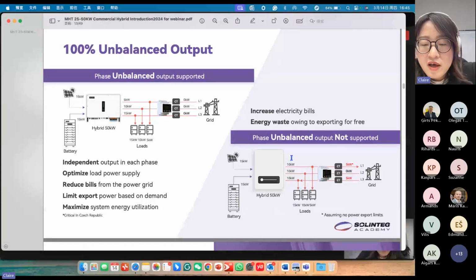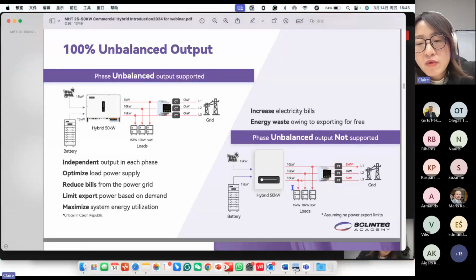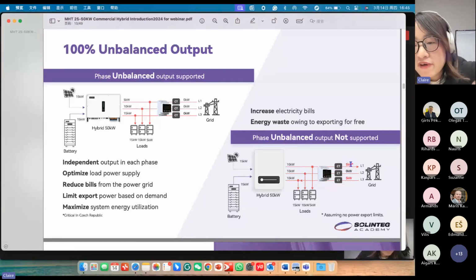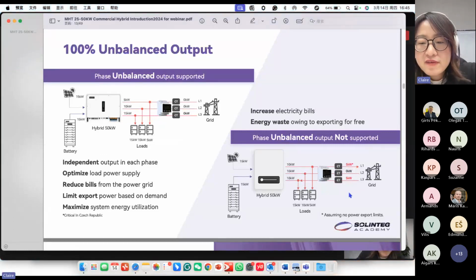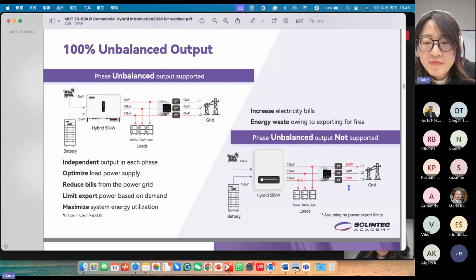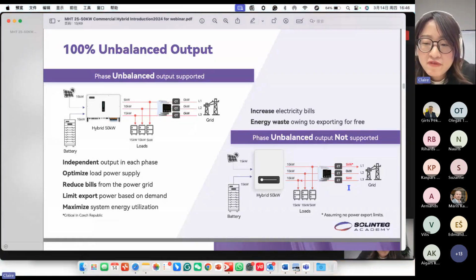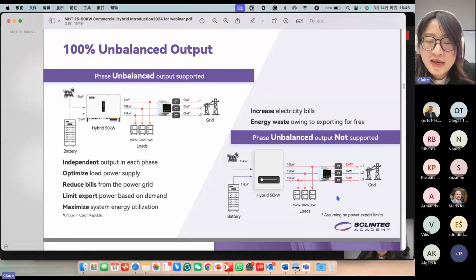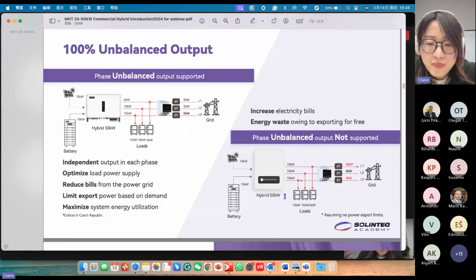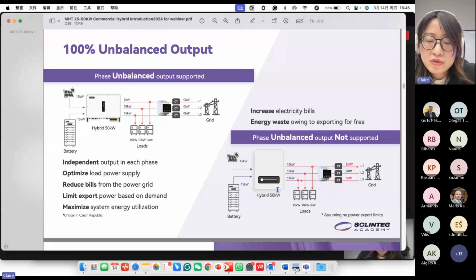If they don't support the unbalanced output, every phase will output the same power. That means the first phase needs to sell 5 kilowatts to the grid. We assume that the country allows the power to go to the grid, so we will sell 5 kilowatts to the grid. And for the third phase, we need to buy 5 kilowatts from the grid. And we know in some countries the power going to the grid may be free of charge. The utility company won't give you any payback, or sometimes they give you a very low tariff. But the power we're taking from the grid is usually very expensive. So this will increase the customer's electricity bills, and also lead to power waste owing to the power export for free.